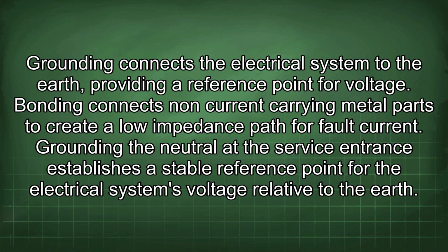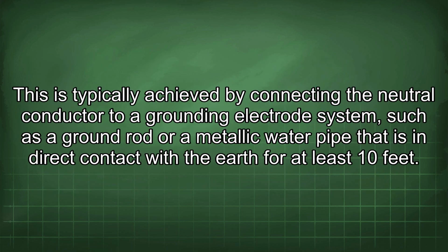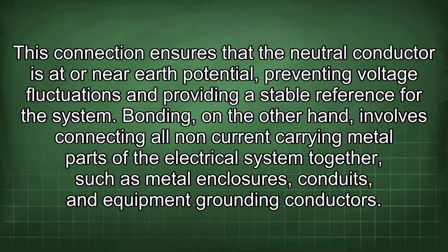Grounding the neutral at the service entrance establishes a stable reference point for the electrical system's voltage relative to the earth. This is typically achieved by connecting the neutral conductor to a grounding electrode system such as a ground rod or a metallic water pipe that is in direct contact with the earth for at least 10 feet.